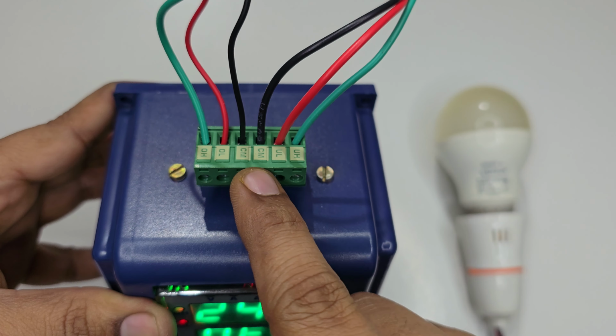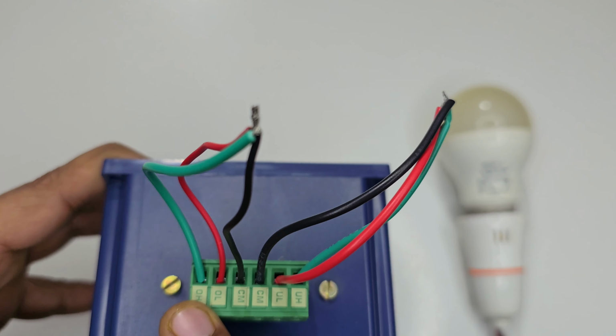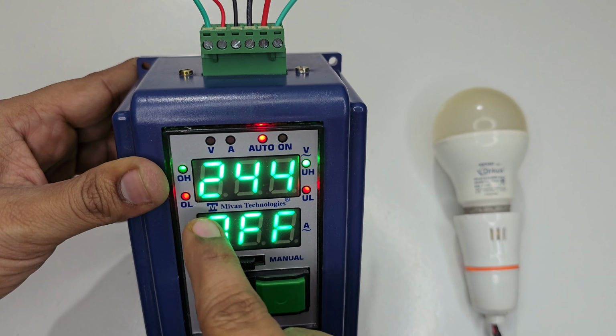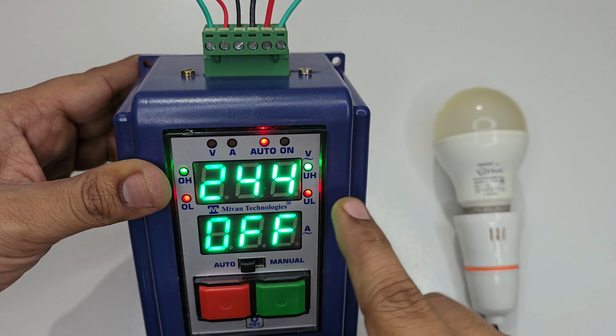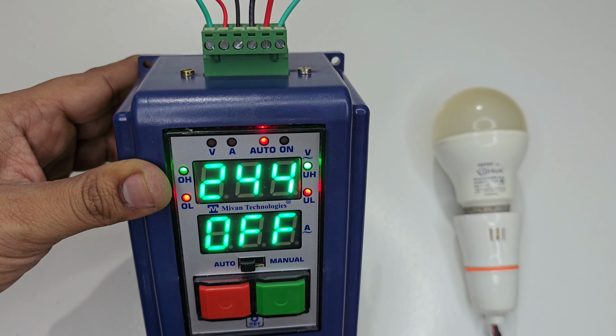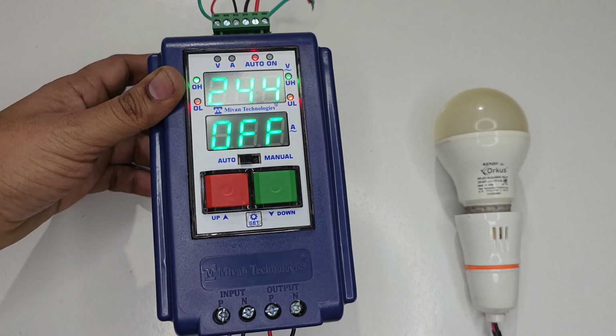When you short all the terminals, these commons are a common wire, so C, OL and OH. When you short the C, OL and OH terminals together, you can see the OL and OH indications and bulbs turn off. If it works, then the unit is working fine in auto mode.